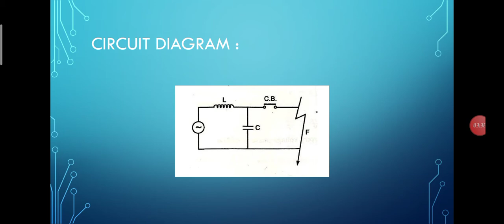The working of current chopping. This can be seen by calculating the formula Vt equals Ic into Z0, where Vt is the voltage transient, Ic is the current chop, and Z0 is the surge impedance. Therefore, if the current chop is 0.9 of an amp and the surge impedance is 3000 ohms, the voltage transient will equal 2700 volts on top of the RMS system voltage, whether it be 4160 volts or 5 kV. The electromagnetic energy stored in the system at the instant before interruption is half L i square.